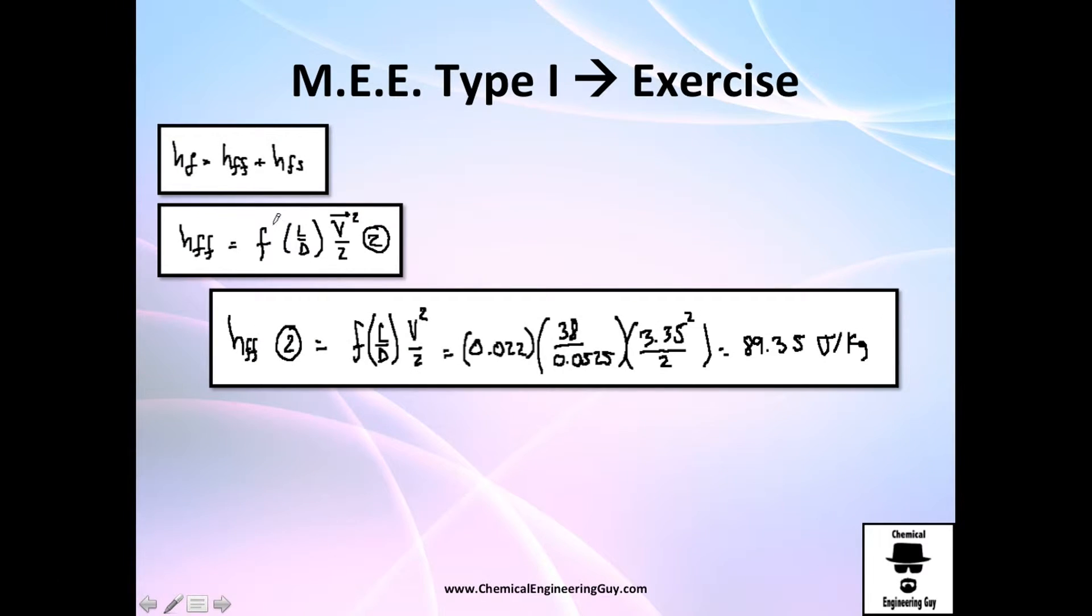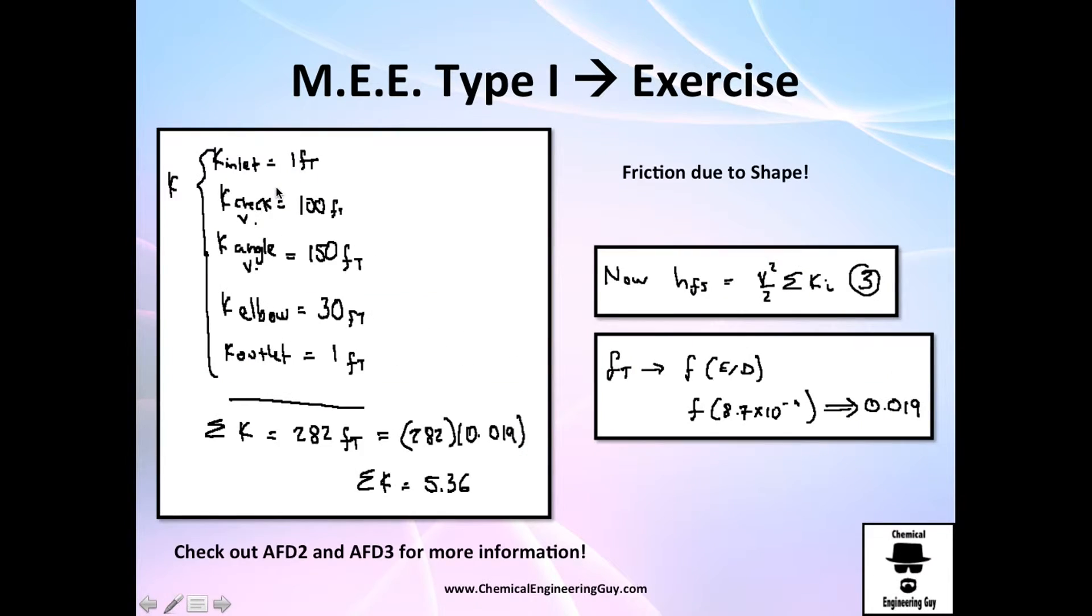Now that was only friction in the wall, I want to calculate the friction due to shape. So I have one inlet which is 1 FT, I have one check valve which is 100 FT, I got one angle valve which is 150 FT, I got one elbow which is 30 FT, and I got one outlet which is 1 FT.